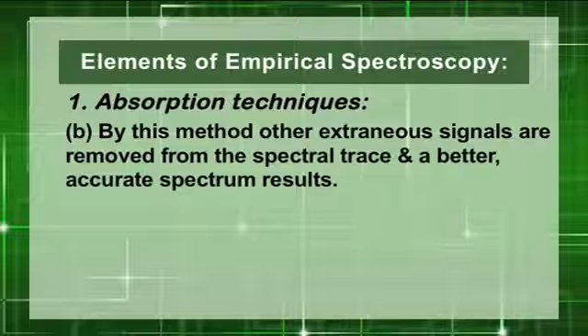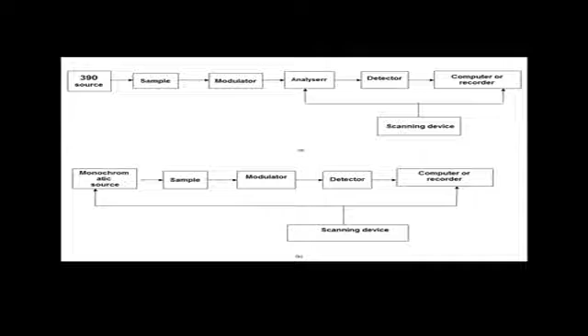In the microwave and radio frequency ranges, monochromatic sources whose emission frequency can be varied over a range are to be selected. Figure shows no analyzer is necessary, the source being in a sense its own analyzer. Now, it is necessary for the recorder to be synchronized with the source scanning device in order that a spectral trace be obtained. This is the typical diagram of a scanning absorption spectrophotometer.